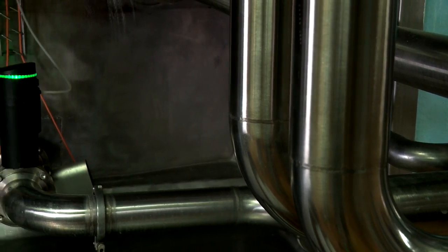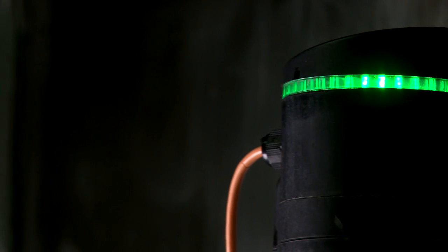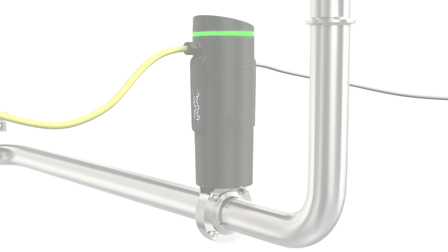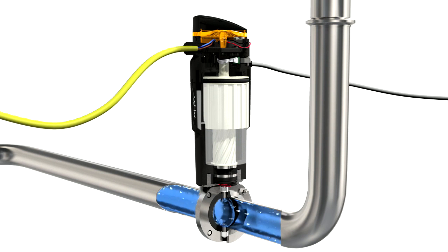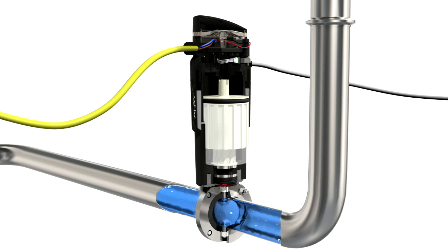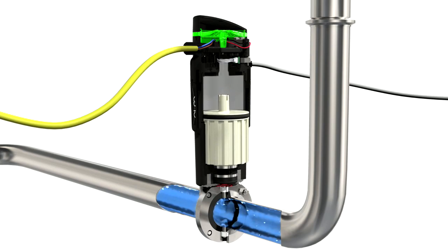The Unique Control makes use of an air spring, which replaces the traditional mechanical spring, ensuring dependable performance and a longer lifetime. When air enters Unique Control, the built-in solenoid valve diverts the flow either on top or below the piston. The helix inside the piston converts the vertical movement to rotation, ensuring smooth operation. The design enables Unique Control to operate at 3 bar air pressure, thereby saving energy.